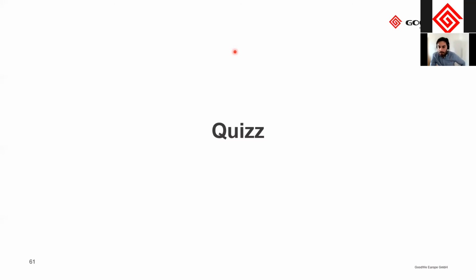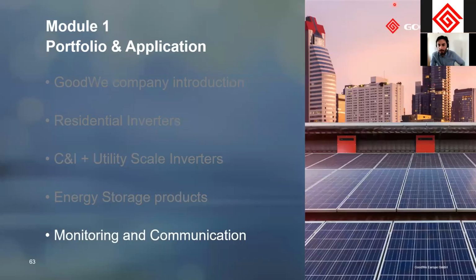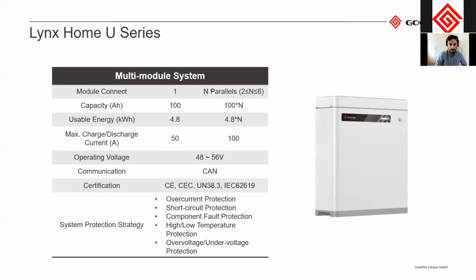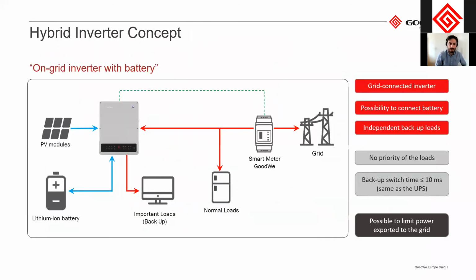So we do have one question here about the connection of the backup loads of the inverter and to the grid. We went through this shortly. I can go back a bit and explain it more thoroughly. I actually think that maybe this is easier to understand. With the backup loads, there are actually 2 AC outputs on the bottom side of the inverter. One is for the backup loads and one is for the normal AC loads. Both are underneath, but basically there's one connection point for the AC load and one AC connection point for the backup loads.